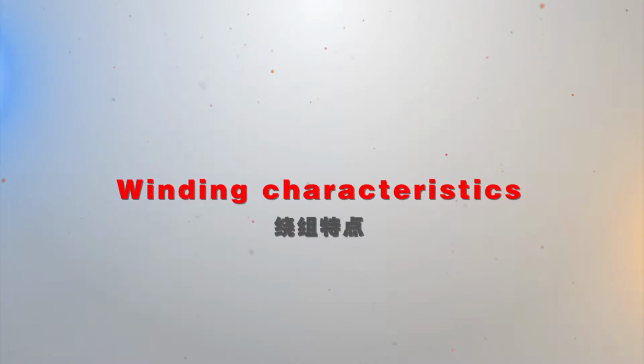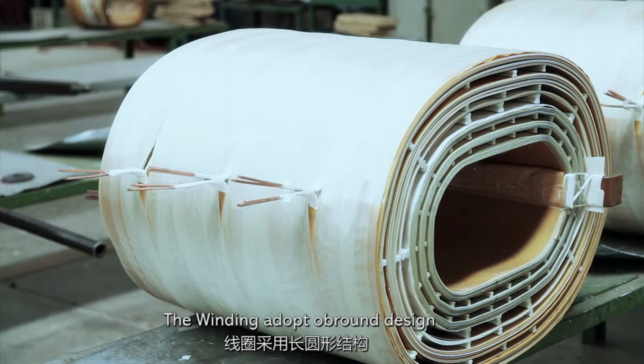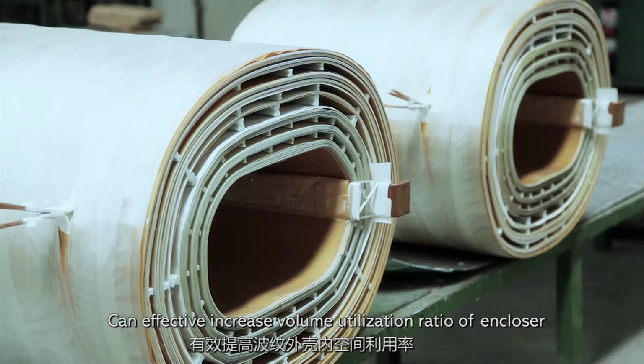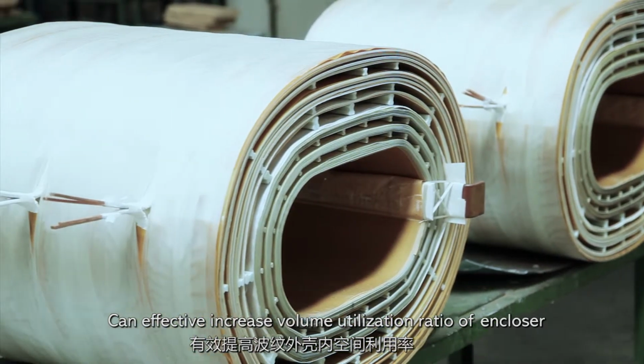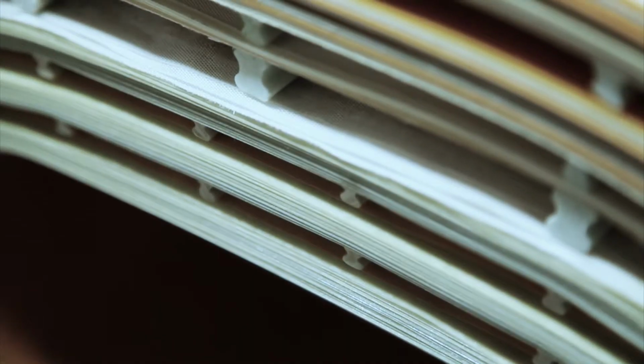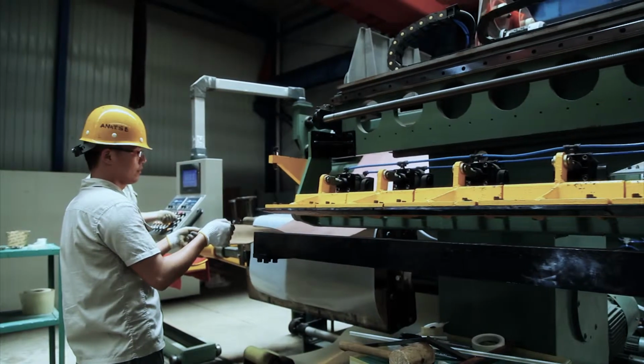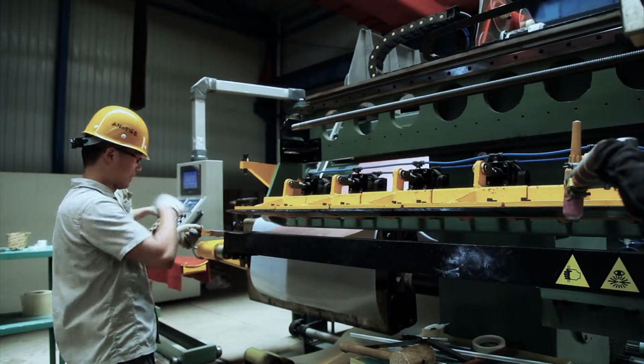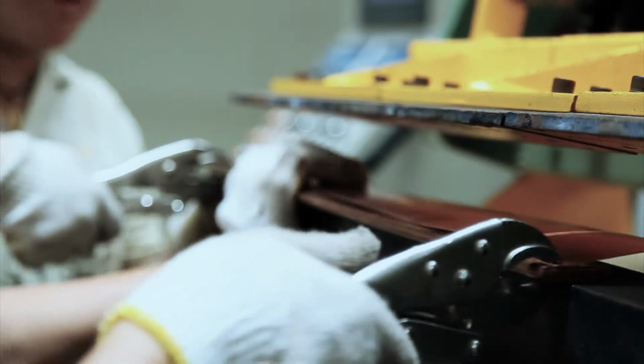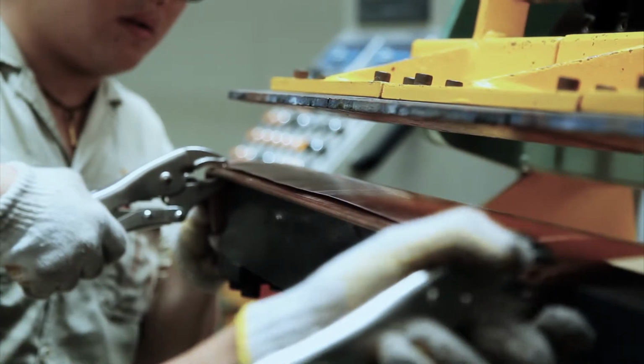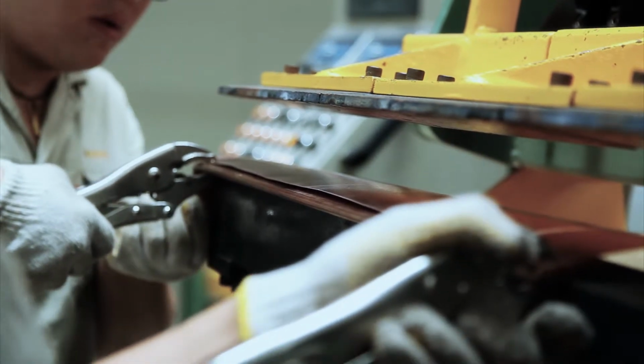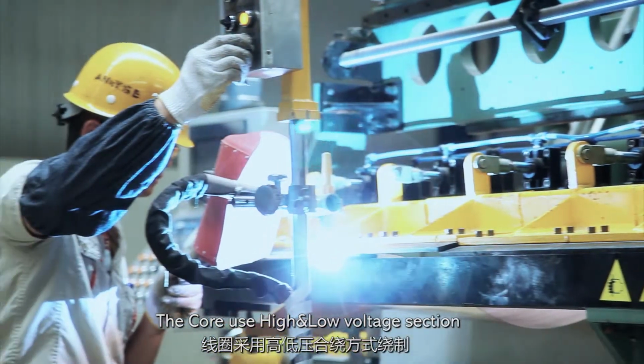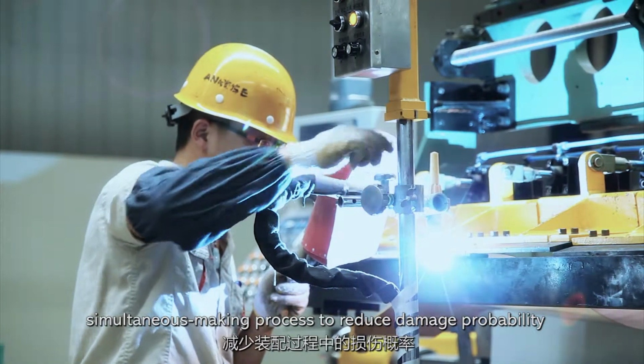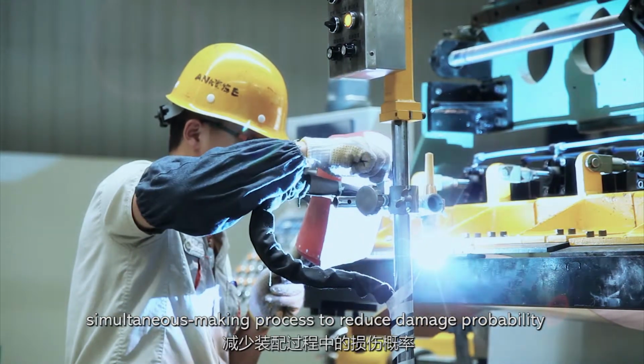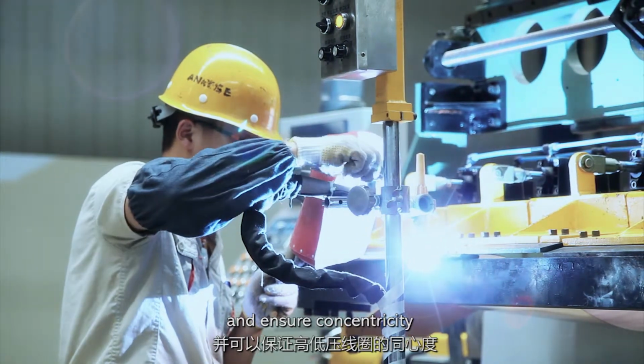Winding characteristics. The winding adopts an oblong design, which can effectively increase the volume utilization ratio of the enclosure. The winding uses a high and low voltage section simultaneous making process to reduce damage probability and ensure concentricity.